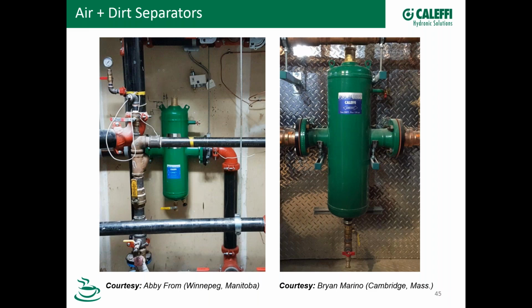Now the other school of thought is if you're connecting a new boiler to an old system that's got maybe iron pipe or cast iron radiators in it, or steel piping that has rust and debris that is going to continue to flake off as that system goes on with the new boiler installed, maybe the better position is on the return, because I'm concerned about catching that sediment and dirt that's going to come out of that system for probably the rest of its life. So that might be one way that you look at it.